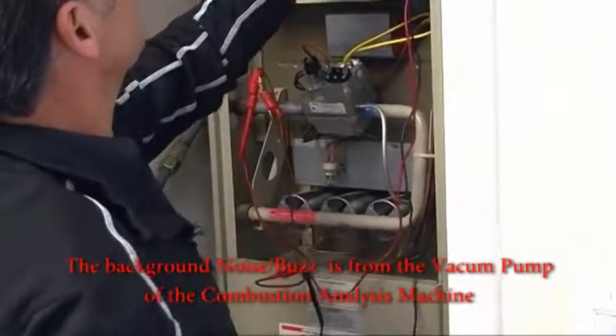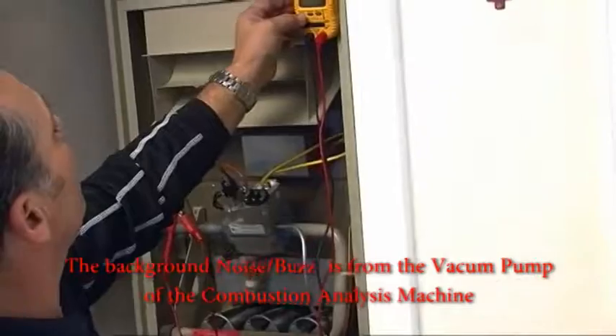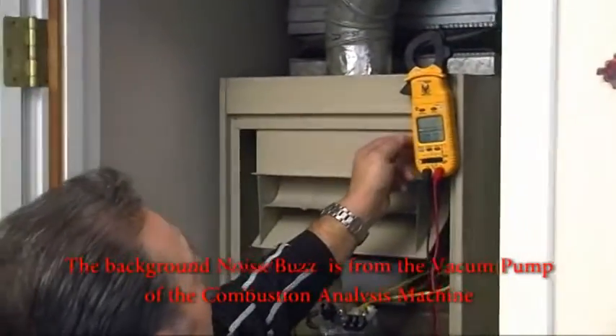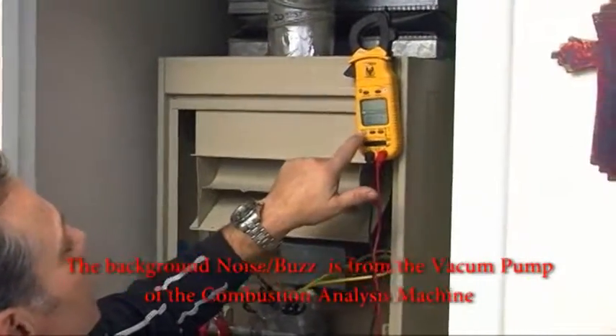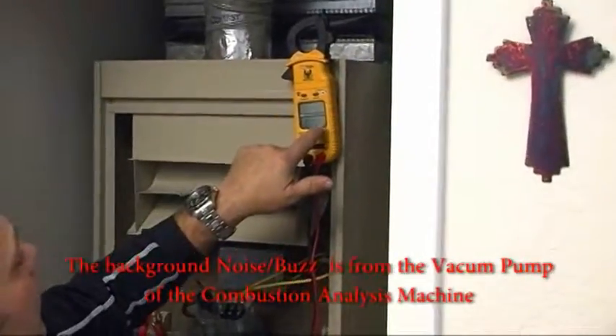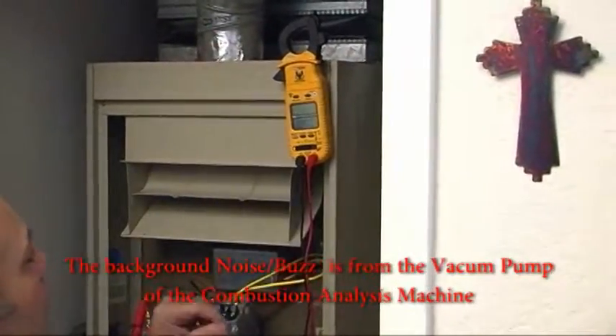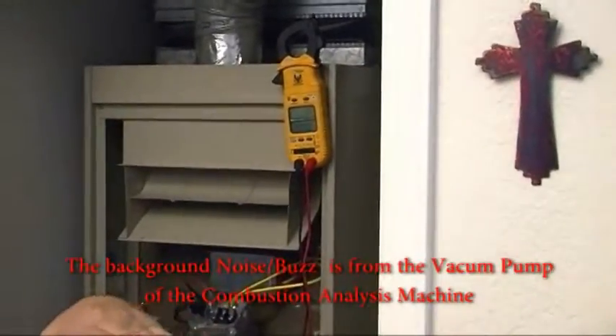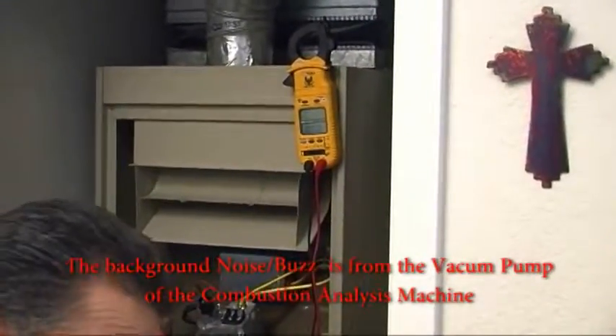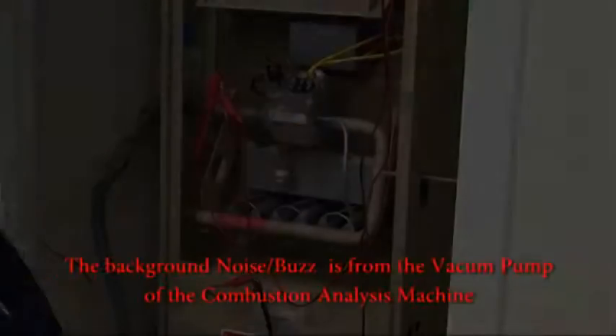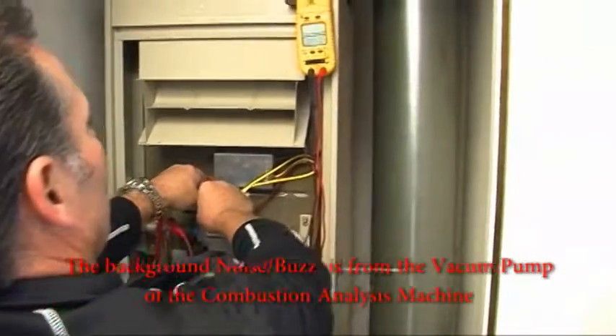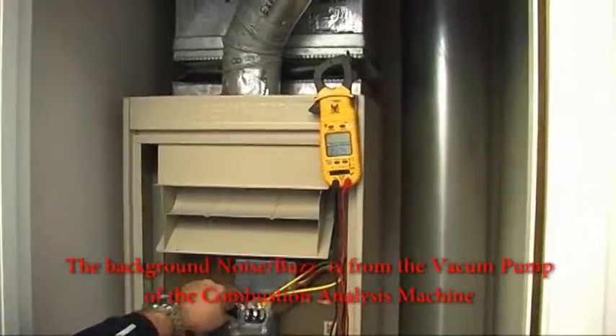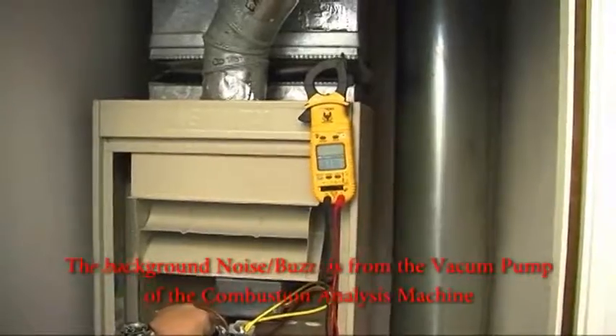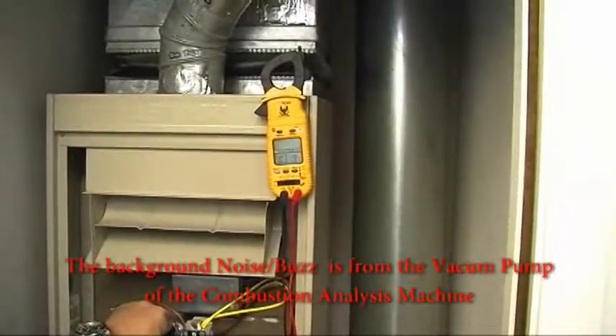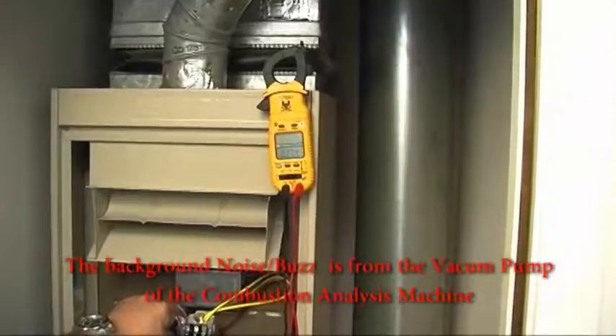I will select millivolts on my machine. You can see the millivolt signal there, the small m with a large V, or the DC voltage is a straight line with three dashes underneath it, okay? So I'm going to need to light this pilot, and we'll do a reading in just a moment. Here we go. We're hooked up correctly. We're at 37.5, 37.8. We have a really strong reading on our thermocouple.